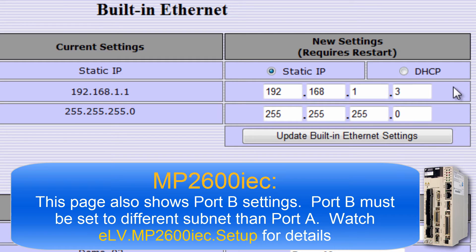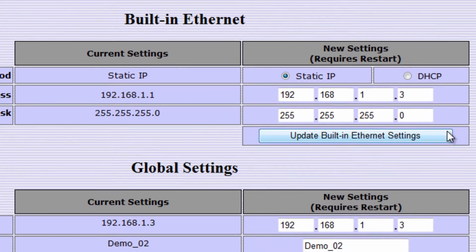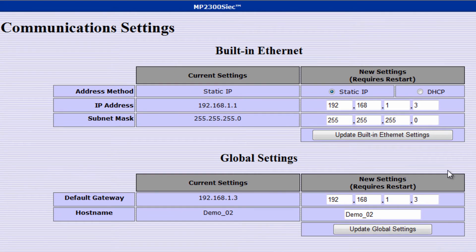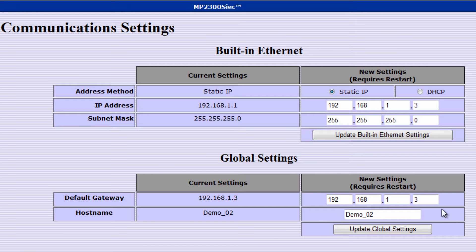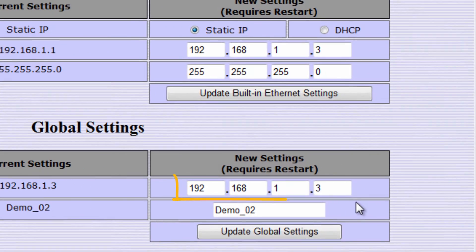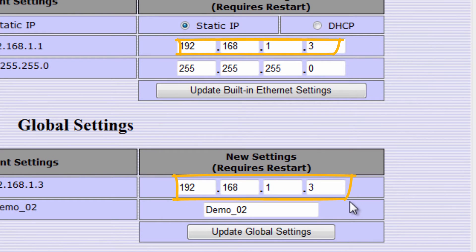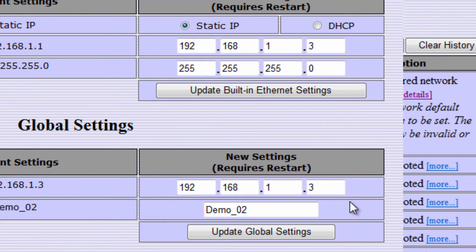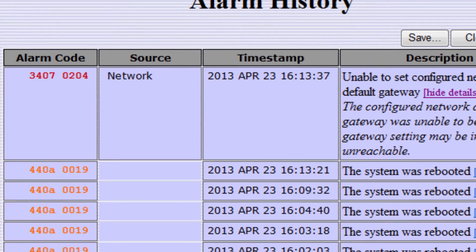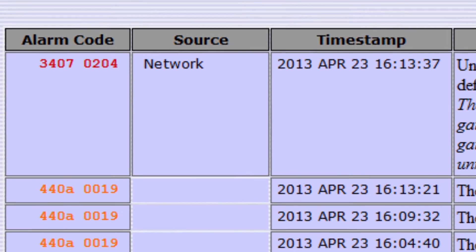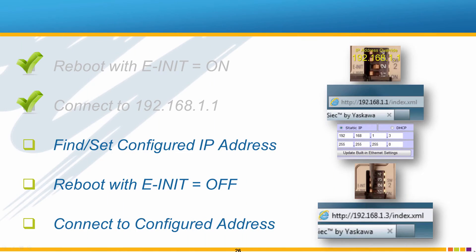The address can be changed here if necessary. The default gateway address is used when the controller is on a network with a gateway device which serves as an access point to another network. If your network does not have a gateway device, set the address the same as the IP address to avoid the gateway not found warning 3407.0204.